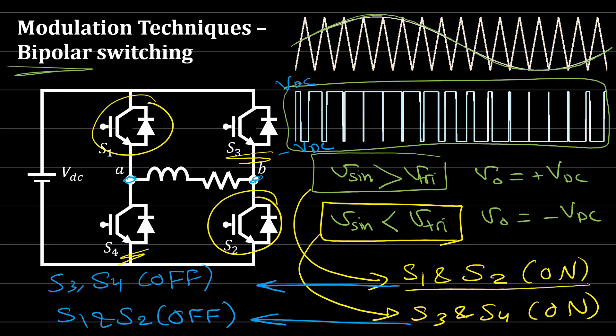Bipolar switching is the simplest modulation technique, but its drawback is that the voltage swings from plus VDC to minus VDC. When you apply an output filter to this waveform, you need a large filter to smooth it into a pure sine wave. For example, with an output of plus 200V to minus 200V, a large filter is required.